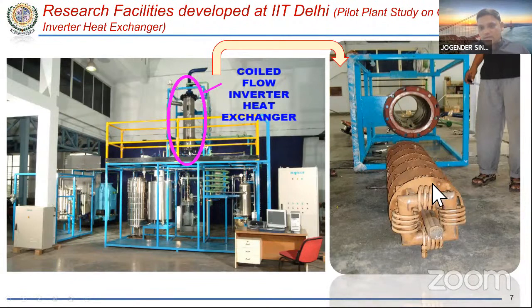So this baffle has a different flow arrangement in the shell side. If this first bank has a baffle cut here, then the second bank has it in the opposite direction. So basically it is diverting fluid inside the shell, so that there is no channeling or loss of mixing happening in the shell side. Okay, so that was ensured there.